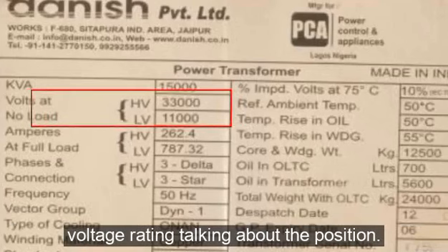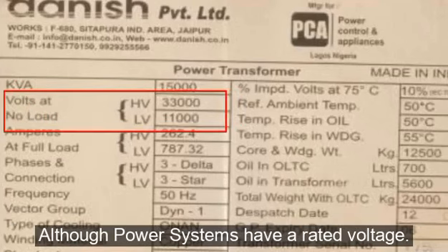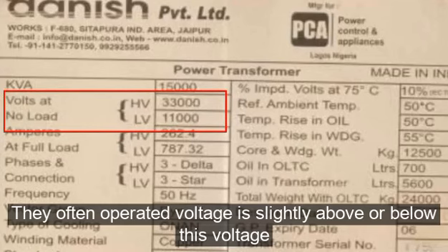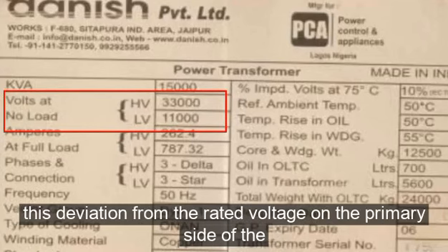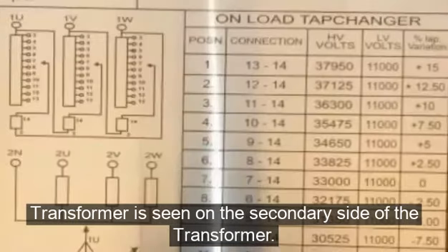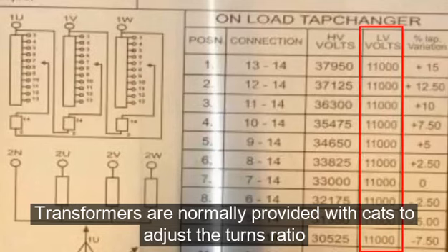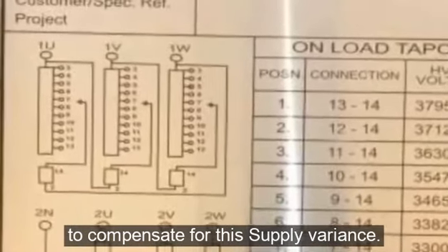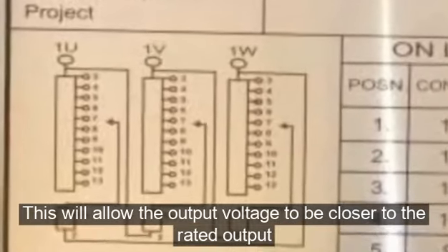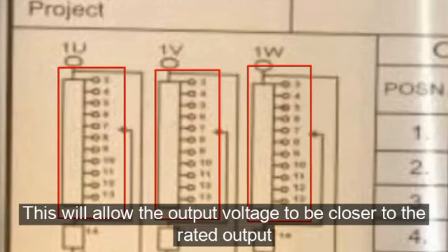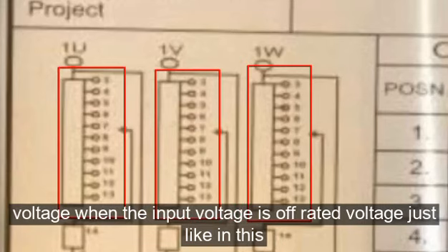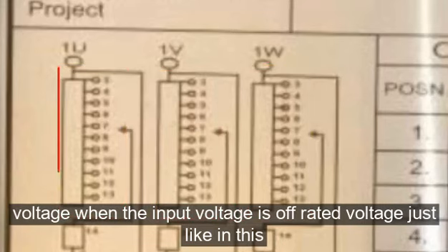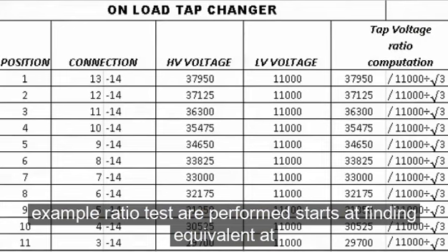Talking about the tap position. Although power systems have a rated voltage, they often operate at voltages slightly above or below this voltage. This deviation from the rated voltage on the primary side of the transformer is seen on the secondary side of the transformer. Transformers are normally provided with taps to adjust the turns ratio to compensate for this supply variance. This will allow the output voltage to be closer to the rated output voltage when the input voltage is off rated voltage. Just like in this example, ratio tests are performed.